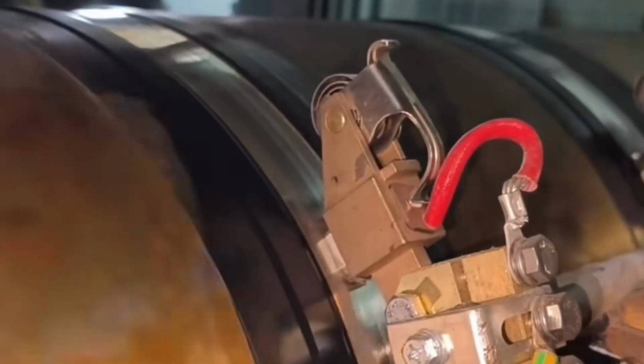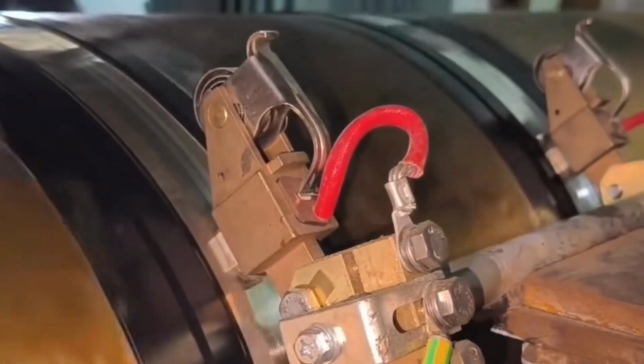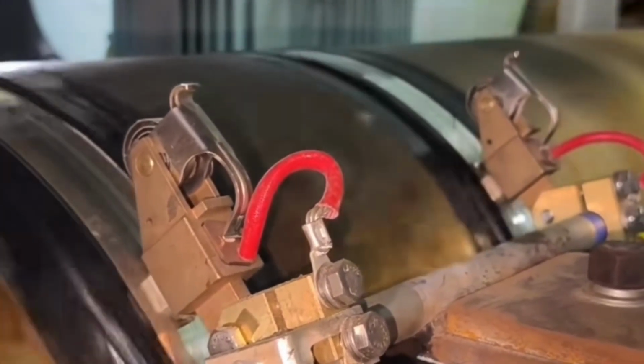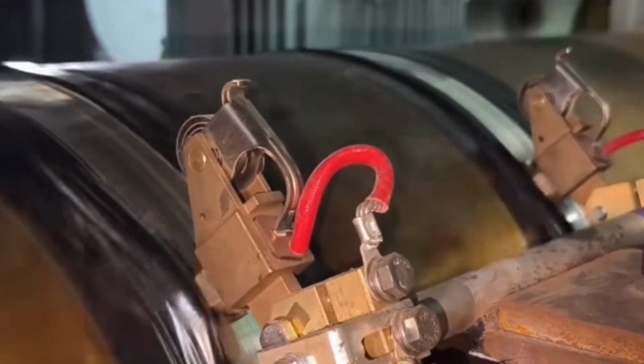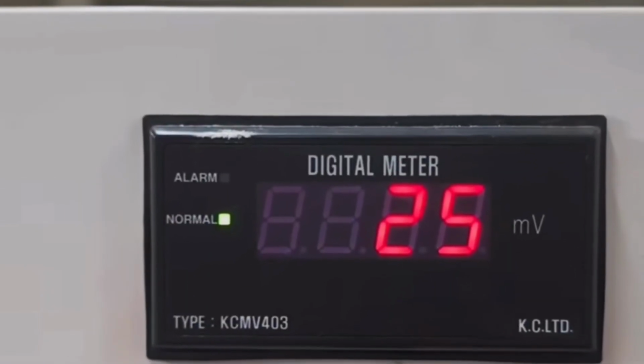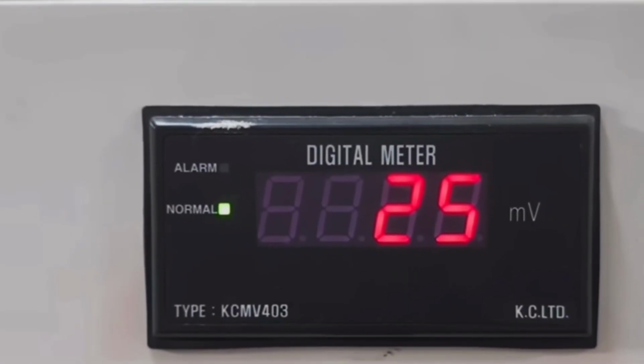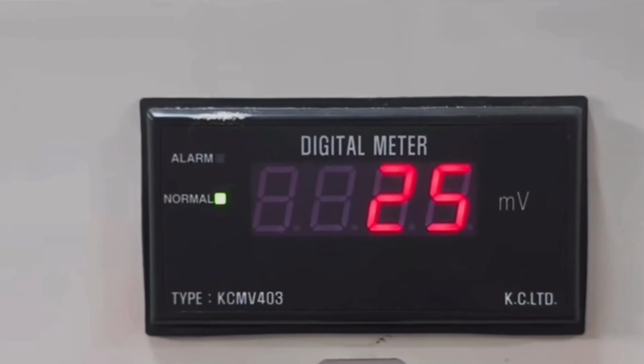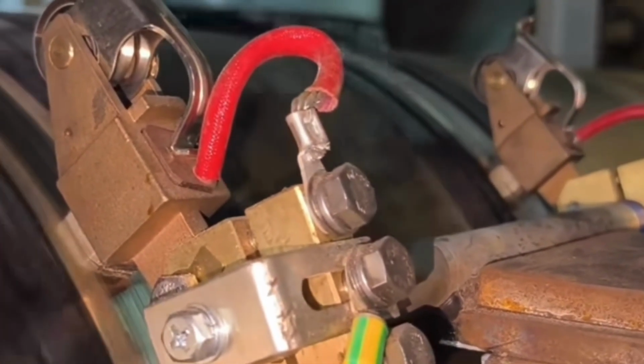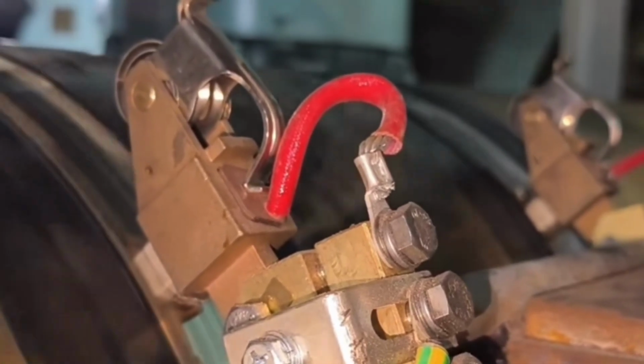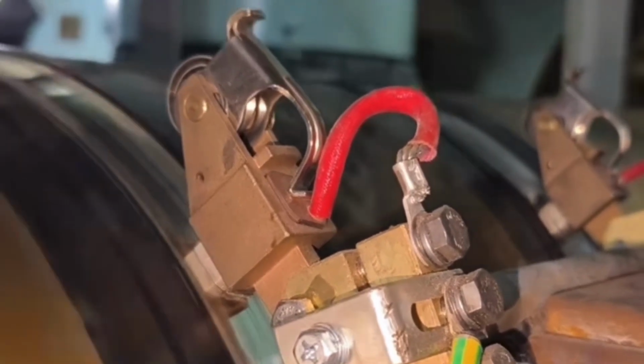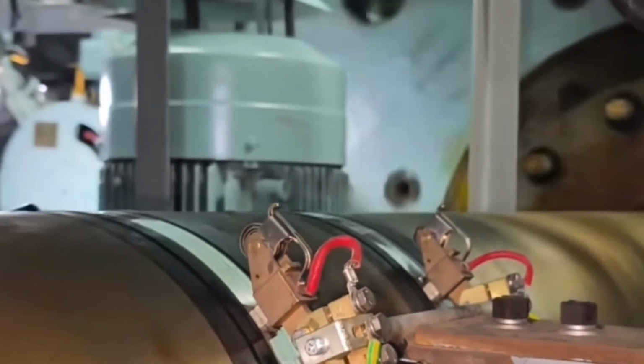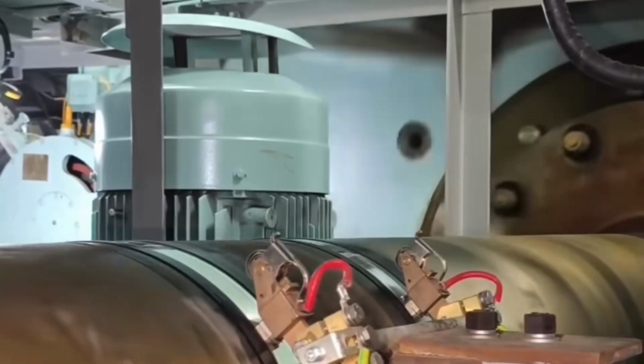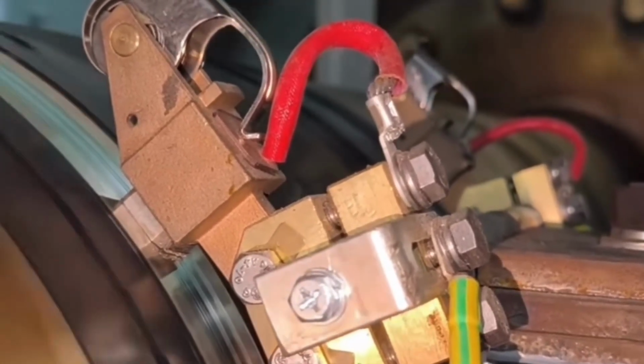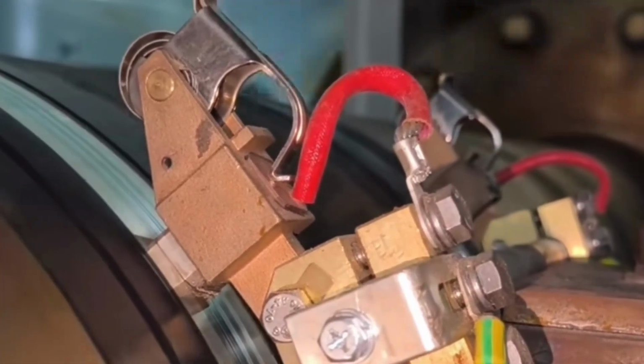The slip rings form the contact surface for the brushes. They are made of conductive material and are carefully aligned with the brushes to ensure smooth electrical flow. This contact allows the current to safely transfer from the rotating shaft to the brush. All the current collected by the brushes travels through the earthing cables, usually visible as heavy red or black insulated wires. These cables connect the brush assembly directly to the ship's hull, completing the grounding path and preventing harmful voltage from accumulating in the bearings.